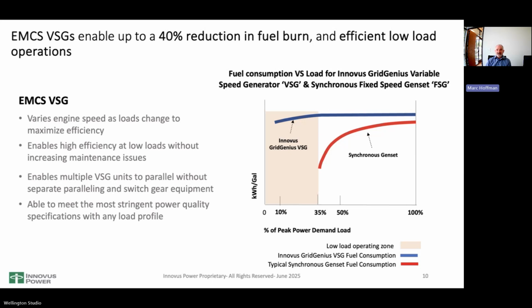You can't do that, so it doesn't just have an implication on fuel efficiency. It has a huge implication on how I deal with it if I have a powerhouse supporting a community where its peak load in wintertime is, say, 700 kilowatts, but in the middle of summer its minimum load is 150 kilowatts. I'll get to how they deal with it today, but there's huge implications because of how synchronous gensets are supposed to operate.